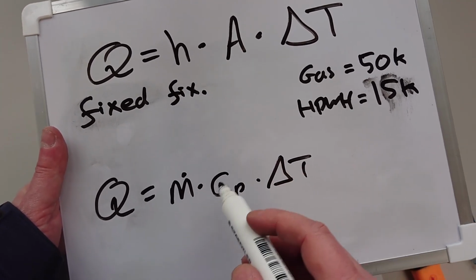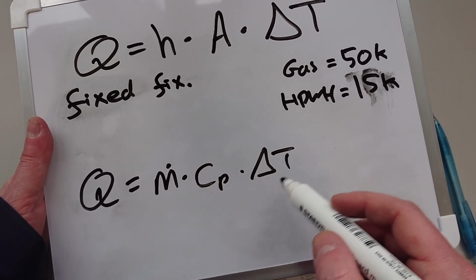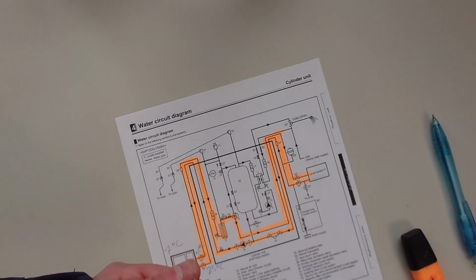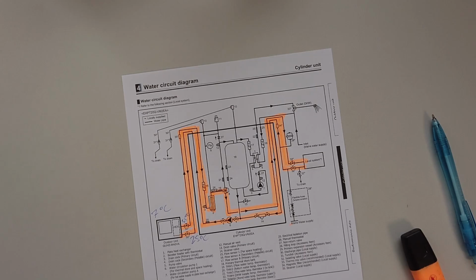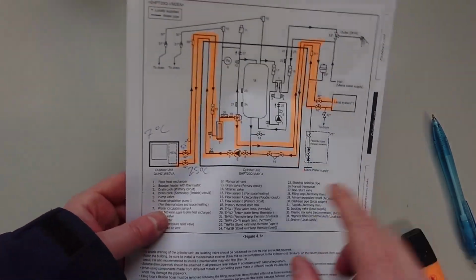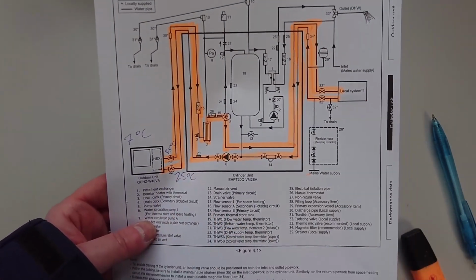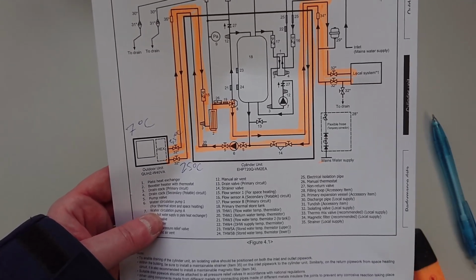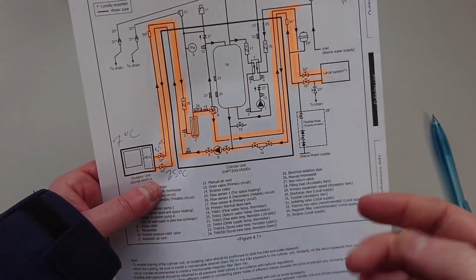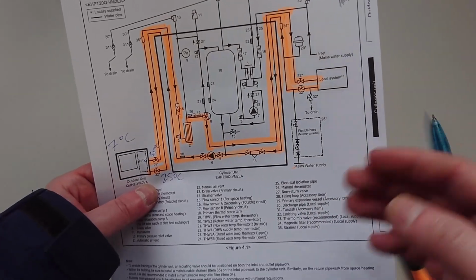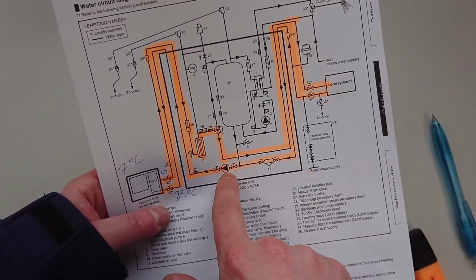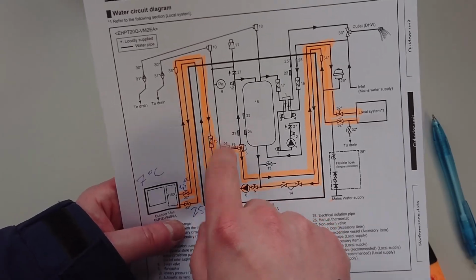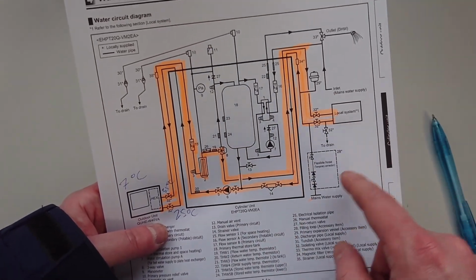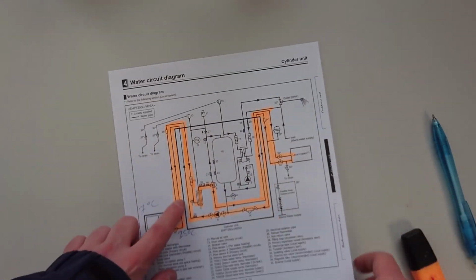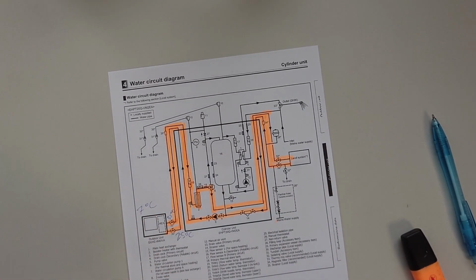And the higher the mass flow you have, if you rearrange this equation, you find that the delta T becomes smaller and smaller. So what that means is that you use your smallish delta T here, which your heat pump is quite efficient at doing because it's a low pressure difference. And the lower your pressure ratio, i.e. the in and the out pressure of your compressor, the more efficient the system is. And all we do is increase this pump speed here and flow more and more water. So you have more water flow, but less temperature difference, and it balances out, or it's the theory that it should balance out anyway.